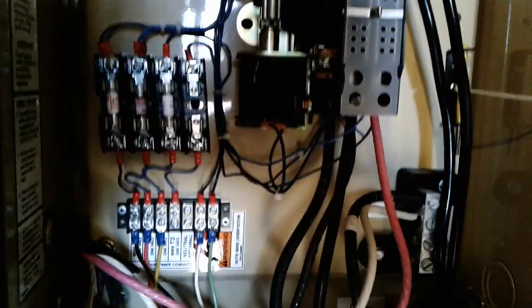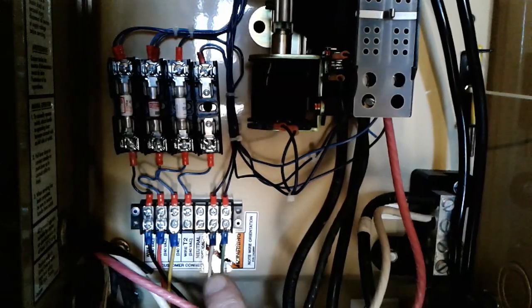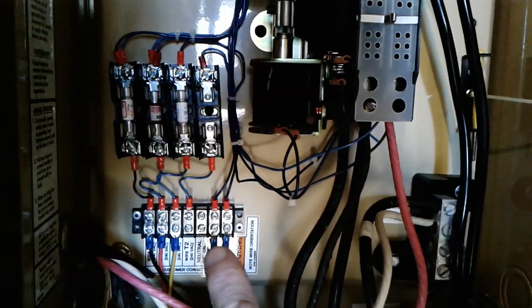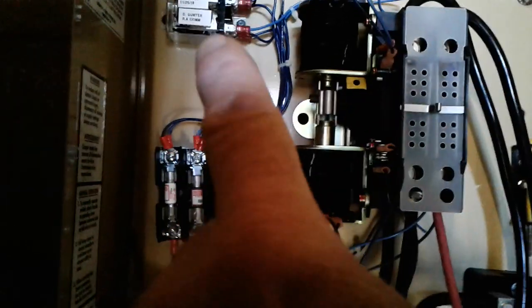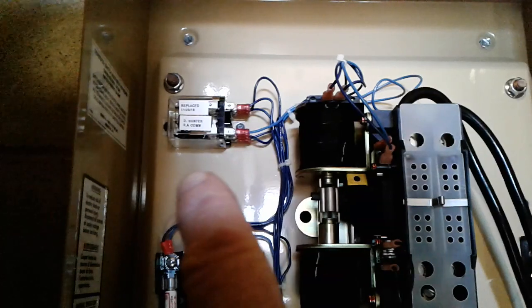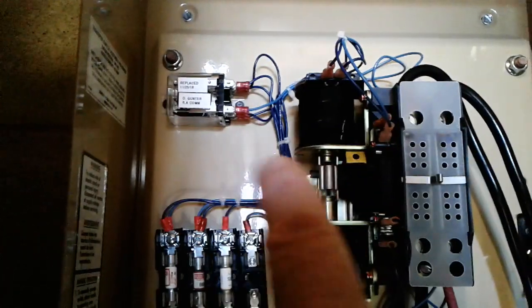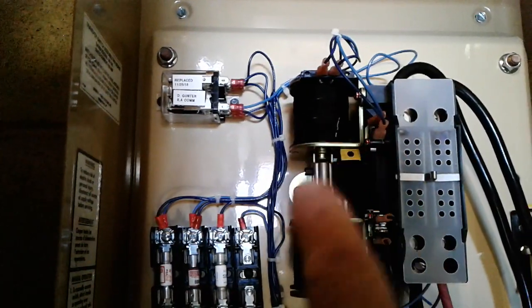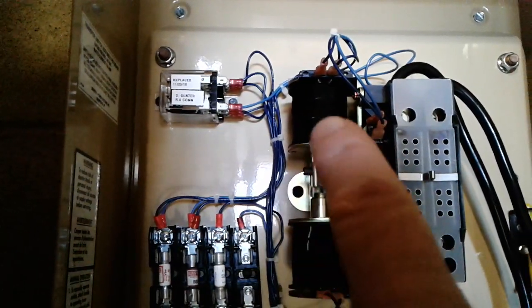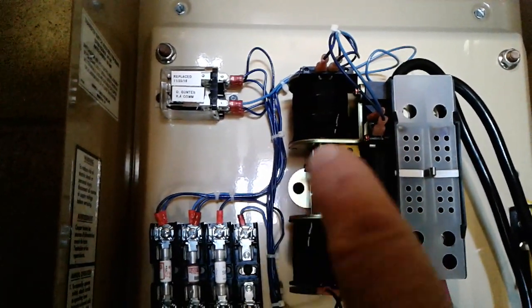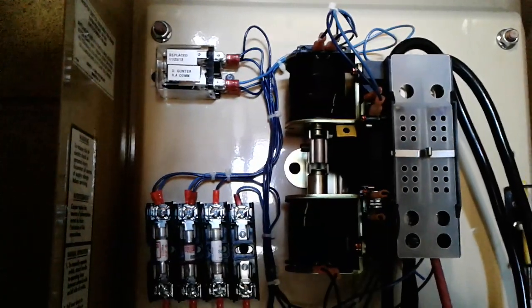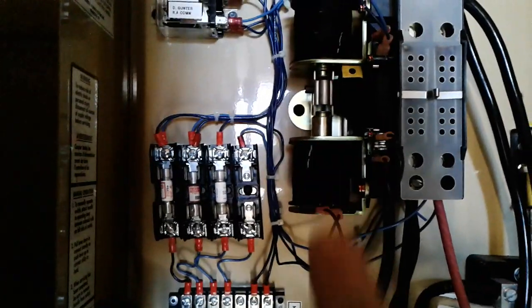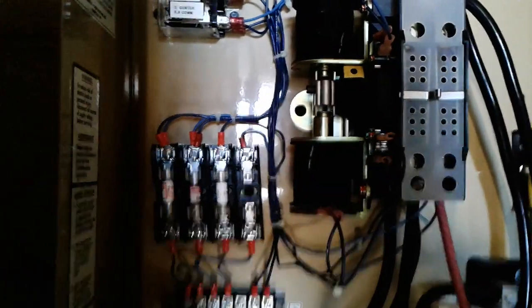There's 12 volts when the generator comes up to speed. 12 volts come through these terminals here. They go up to the relay which controls the AC flowing through the coils. Either this upper set pulls at the mains, or this lower set will pull at the generator.